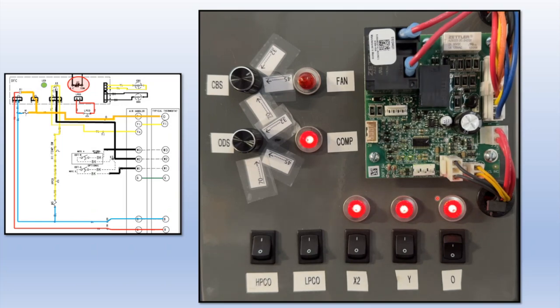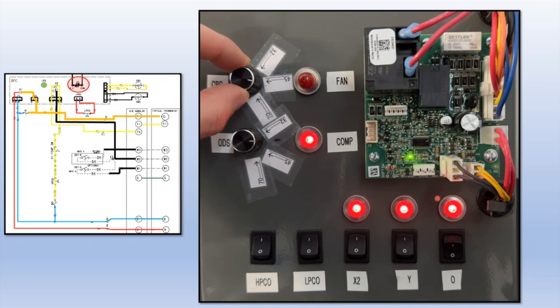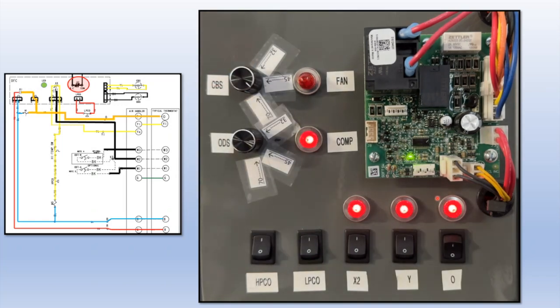So this defrost cycle is going to last until the coil sensor reads that it's gone above the termination temperature, factory being 47 Fahrenheit. So we're going to adjust that above 47 Fahrenheit, where we see the outdoor fan came on. That's going to lower the head pressure that's been building up during the defrost, so it's not such an aggressive switchover. That's going to be for 12 seconds before the reversing valve is de-energized, as well as the X2, putting it back into the normal heating mode of operation.